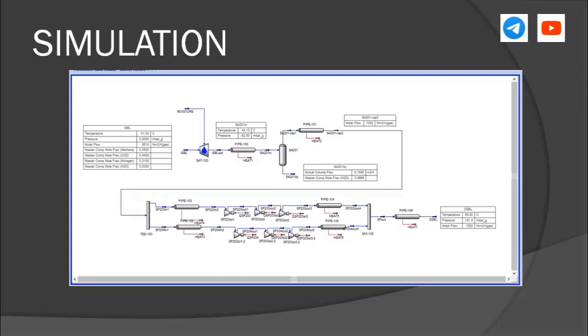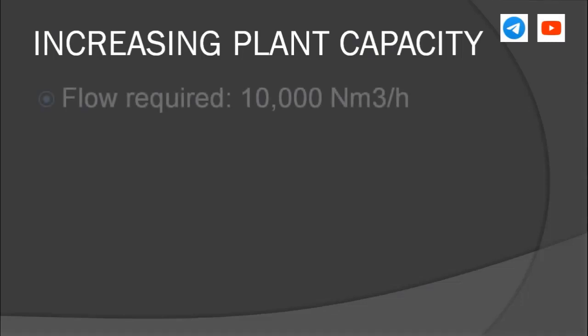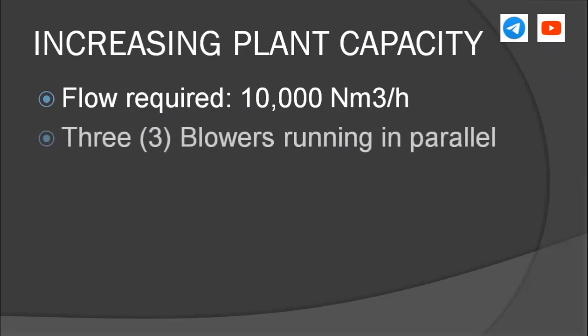Up to this point, it was only gathering information and understanding the scope in order to do the real job, that is, increase the plant capacity. Just to remind you, we need to increase plant capacity from 7,500 normal cubic meters to 10,000 normal cubic meters. To do that, we will run three blowers in parallel instead of two.